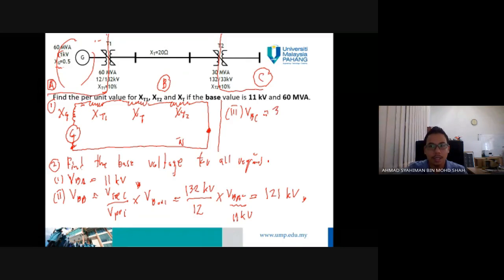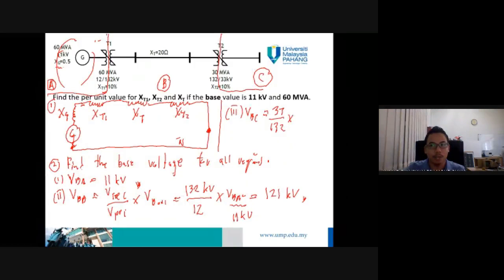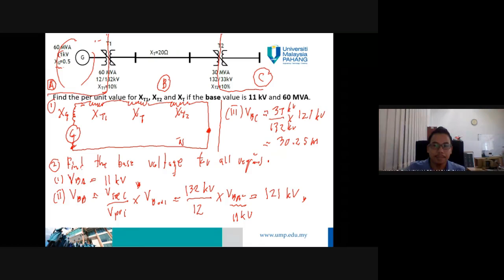So it becomes 33. Still the same: secondary over primary, 33 over 132, multiplied by VB original, which is VBB, 121 kV. Using your calculator: 33 over 132 multiplied by 121, you get 30.25 kV. So this second step is to find the base voltage for all regions: VBA is 11 kV, VBB is 121 kV, and VBC is 30.25 kV. Until this level, do you have any questions?